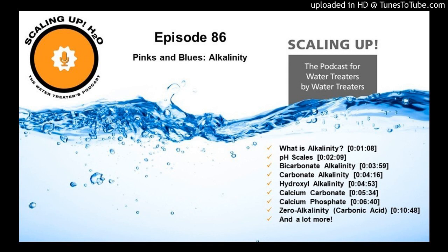Now, what do we do to make sure we don't have carbonic acid in the water or in the condensate? Well, we put something that goes over with the steam to increase the pH. Why do we increase the pH? Because we can't have carbonic acid over particular pHs, and most of our systems are at 8.3, so we even get the bicarbonate alkalinity out, so we don't have enough free alkalinity in there to actually convert to carbonic acid in the presence of carbon dioxide.